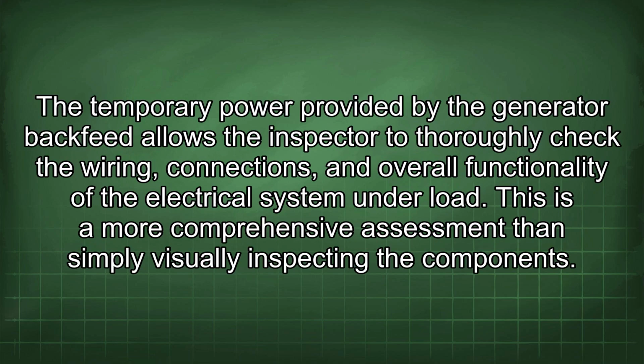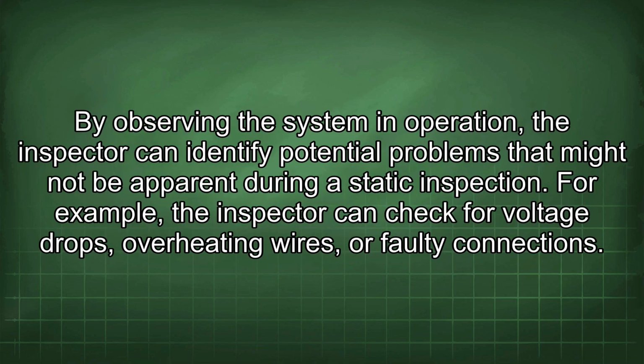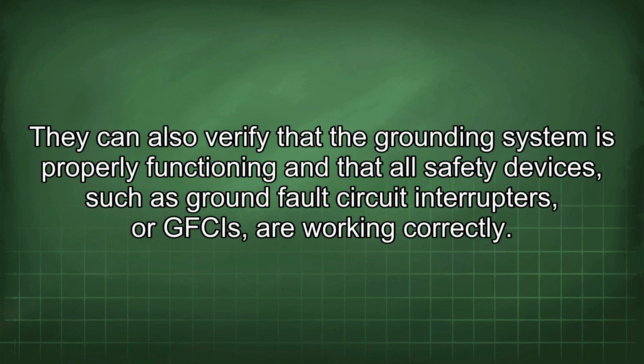The temporary power provided by the generator backfeed allows the inspector to thoroughly check the wiring, connections, and overall functionality of the electrical system under load. This is a more comprehensive assessment than simply visually inspecting the components. By observing the system in operation, the inspector can identify potential problems that might not be apparent during a static inspection. For example, the inspector can check for voltage drops, overheating wires, or faulty connections. They can also verify that the grounding system is properly functioning and that all safety devices, such as ground fault circuit interrupters or GFCIs, are working correctly.